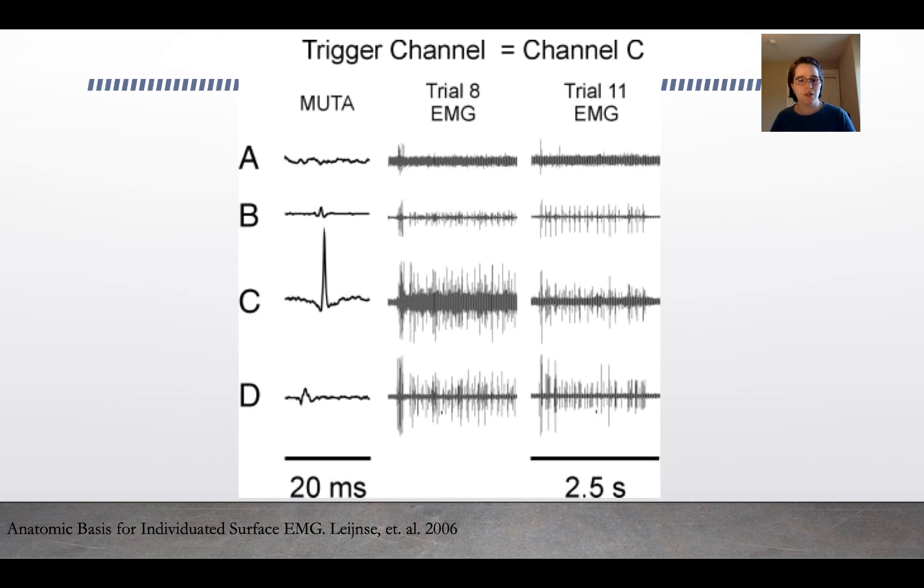There's also a challenge with EMG of crosstalk. If you're using multiple electrodes, sometimes one electrode will pick up the signal being transmitted in another electrode. That's a process called crosstalk where you have talk between the electrode wires. You can see that in this figure here where channel C is affecting several of the other channels, in particular channel B.